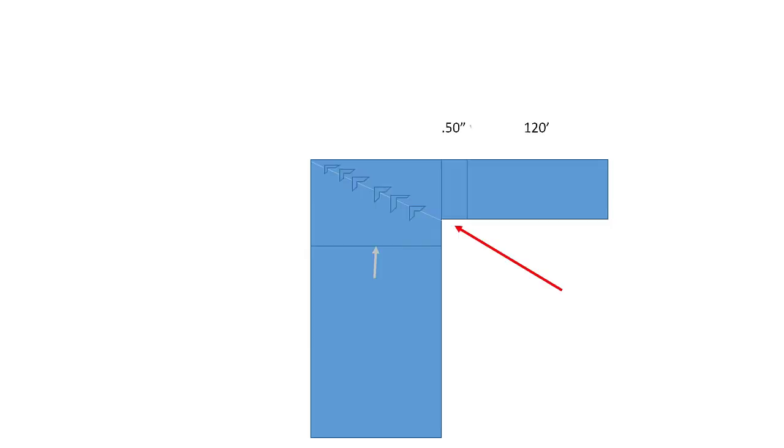By installing turning vanes properly, we can reduce that fitting friction from 120 equivalent feet to 20 feet.